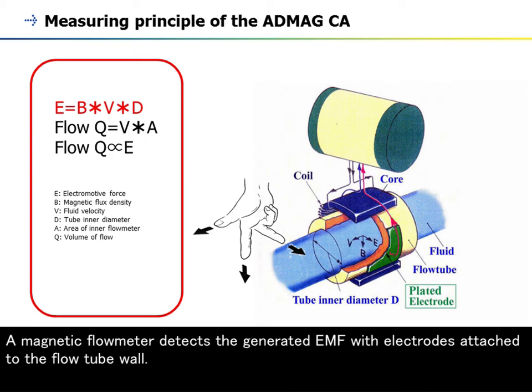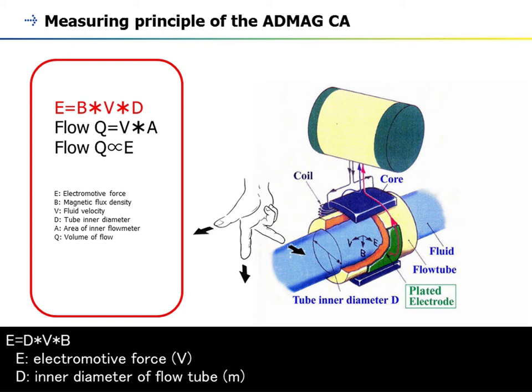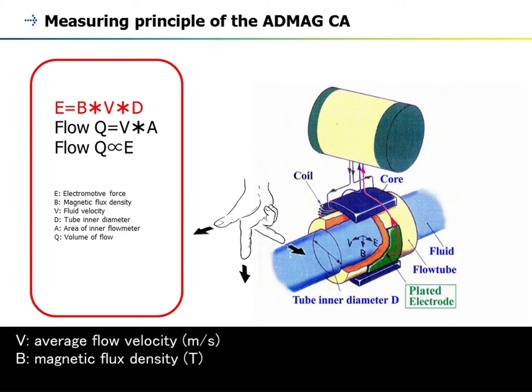A magnetic flow meter detects the generated EMF with electrodes attached to the flow tube wall. The formula is: E equals D times V times B, where E is electromotive force in volts, D is the inner diameter of the flow tube in meters, V is the average flow velocity in meters per second, and B is the magnetic flux density in Tesla.